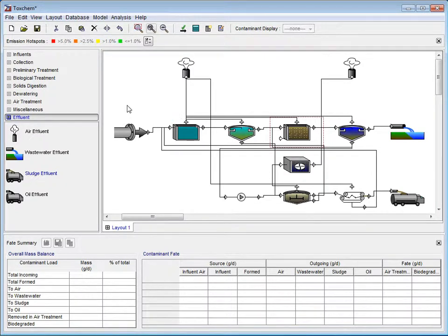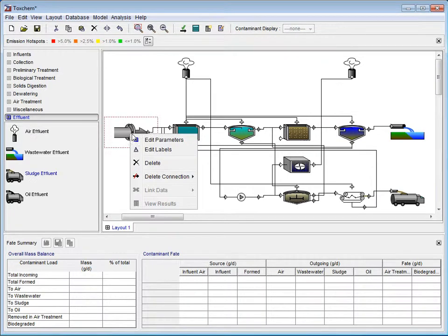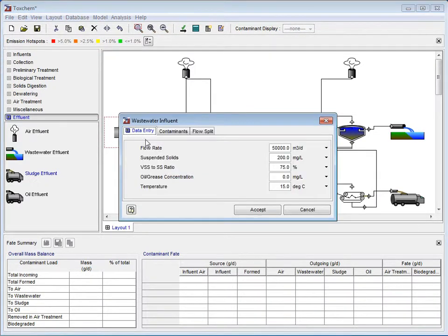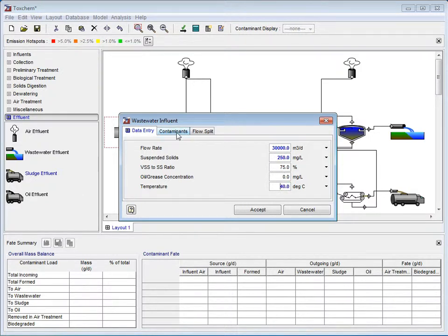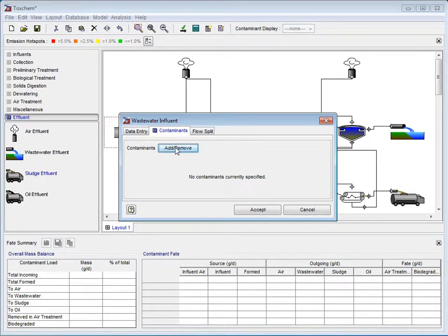To start, we right-click on the wastewater influent and select Edit Parameters from the drop-down menu. In this example, we will alter the flow rate by typing in 30,000 meters cubed per day, the suspended solids to 250 milligrams per liter, and the temperature to 40 degrees Celsius.